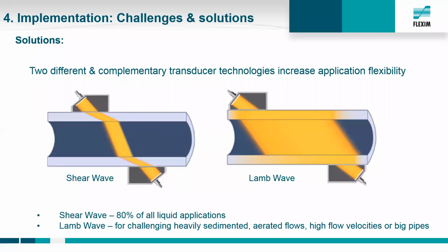The lamb wave, displayed on the right side, transducers generate an ultrasonic pipe wall resonance, which is generated in the pipe material and moves along the pipe. The pipe is emitting the lamb wave into the water. The advantage of a lamb wave is the broad signal, which is less sensitive to high flow velocities, beam shifts, impurities. Both technologies are based on the transit time principle, but are different approaches to how to emit the ultrasonic signal and how to do the signal propagation.